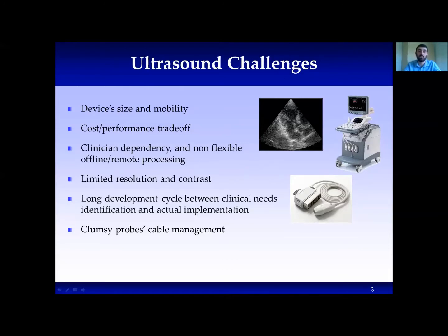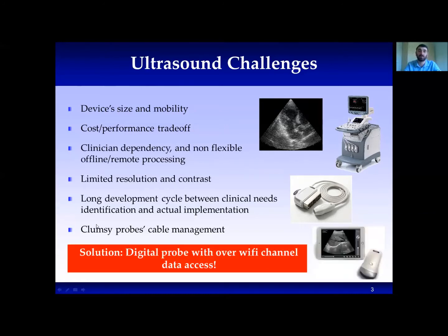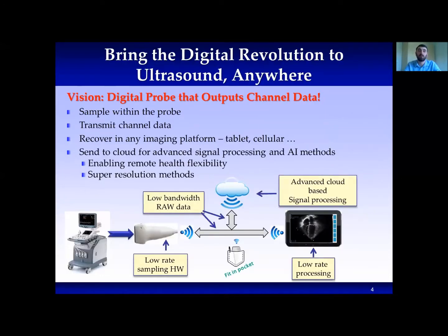Therefore, our vision is to create a digital probe with over-Wi-Fi channel data that will make ultrasound imaging much more preferred in real life. Our idea is to sample at low rate within the probe and transmit the data over Wi-Fi to another platform, like a tablet, smartphone, or a remote computer, and then the image is recovered on the platform based on advanced signal processing algorithms.